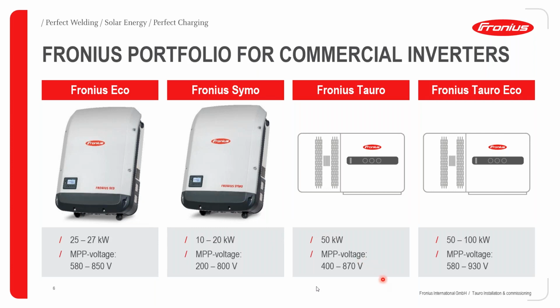Now, in addition to that, we are very excited about the new series of commercial inverters, the Fronius Tauro and the Fronius Tauro Eco. The Fronius Tauro will be available in the 50 kilowatt power range, and the Tauro Eco in the 50 to 100 kilowatt power classes. The Tauro differs from the Tauro Eco in the number of MPPTs. The Tauro will have multiple MPPTs, up to 3, whereas the Tauro Eco will have only 1 MPPT embedded. In terms of the MPP voltage, the Fronius Tauro 50 kilowatt has an operational voltage for MPP from 400 to 870 volts, whereas the Tauro Eco has a range of 580 to 930 volts DC.